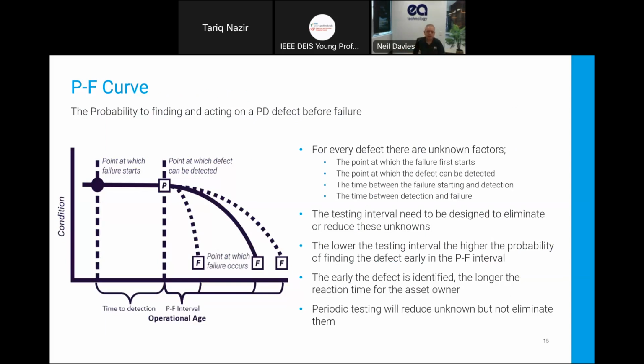Now, what you really want to do is have a testing interval designed to eliminate or reduce as many of these unknowns as possible, and lowering the testing interval will increase the probability of finding a defect early. But we know that permanent monitoring is not always the optimum, costly way forward for all types of switchgear or all types of assets, really. But the earlier we can detect and identify that defect, the longer the reaction time we've got, and the more information we have in terms of, do I need to go in there now, or what? How is it progressing over time?